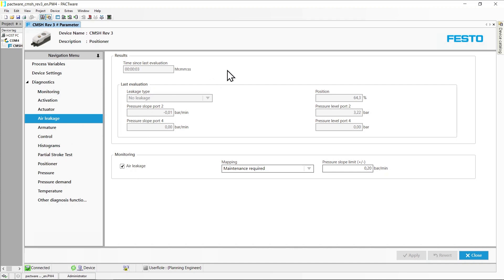The function air leakage evaluates the pressure signals at the actuator ports when the actuator displacement has been constant for several seconds. Secondly, no position change is requested. This means that pressure in the actuator chambers should be kept stable. The observed changes in actuator pressures can then be used to infer the extent of pneumatic leakage.